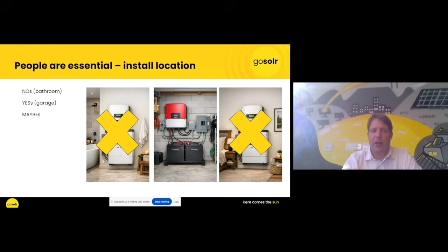Then in the regulation there are some maybes, some gaps. What we try to do there is come up with clear guidelines, often adopting a conservative view. For example, you never install in a bedroom, but it would be easy to say a room is not a bedroom but a storeroom that's not used. Well, it might be used in the future, so no, you can't do that. That's what we're trying to do with installers, to avoid risk today, but also in 2, 5, 10 years down the line.